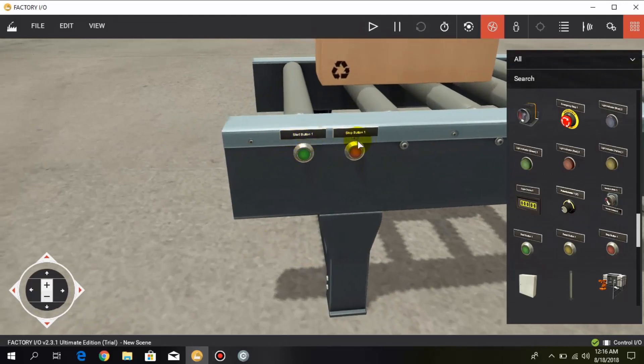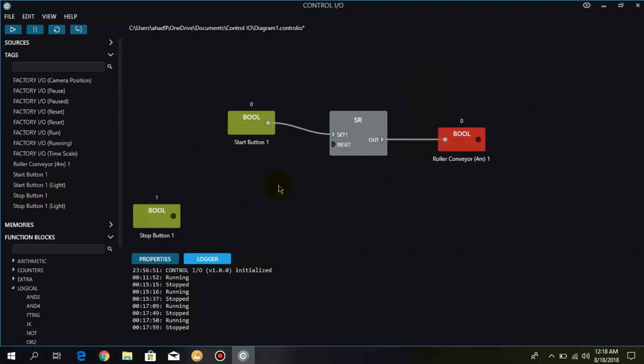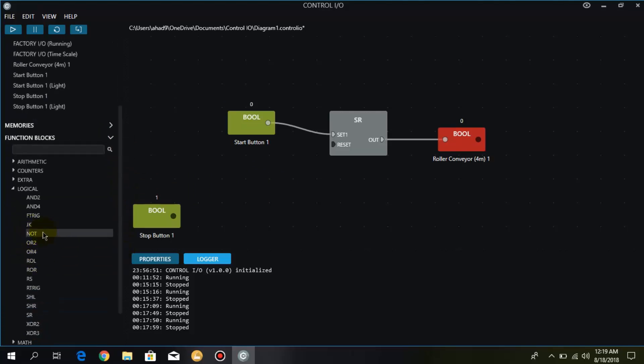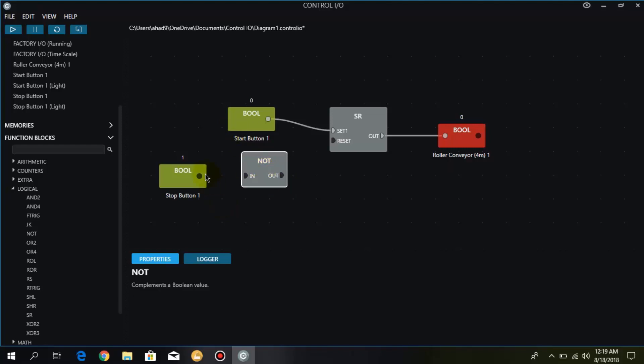Now we have two push buttons: the start push button and the stop push button. I go to Control IO and in the tags I search for the stop push button. One important thing to keep in mind: the stop push button is normally closed. For that we need a NOT logic, which we can find in the logical section. The NOT block means when the stop button is turned on the output is off, and when the stop button is off the output is on — because the stop button is normally closed, whereas the start button is normally open and needs no NOT function. I connect this stop button with the NOT input and the NOT output with the reset.